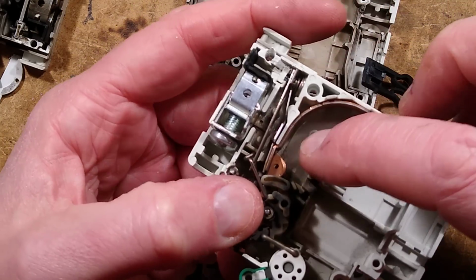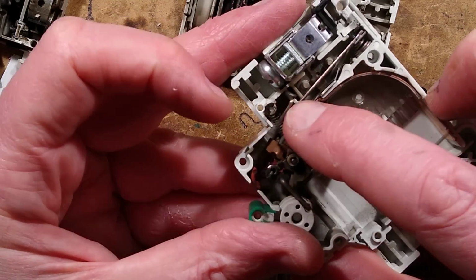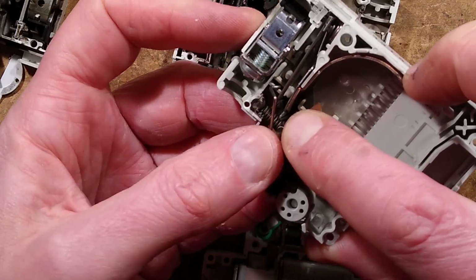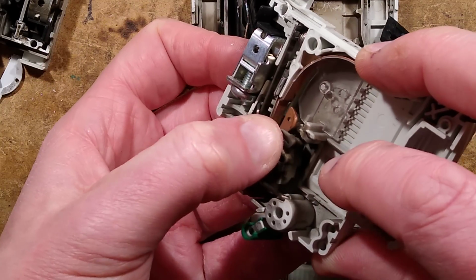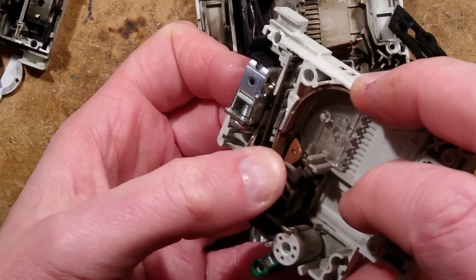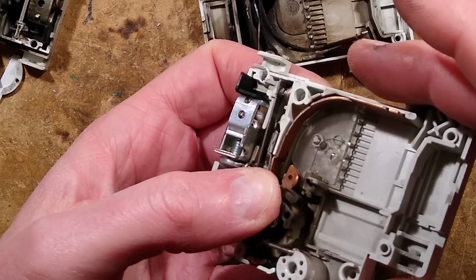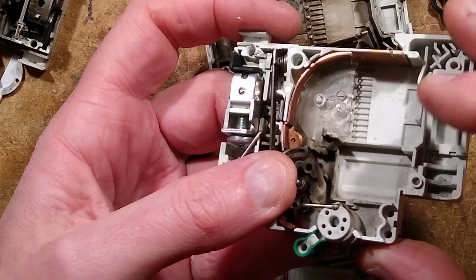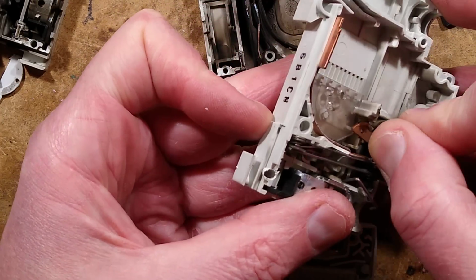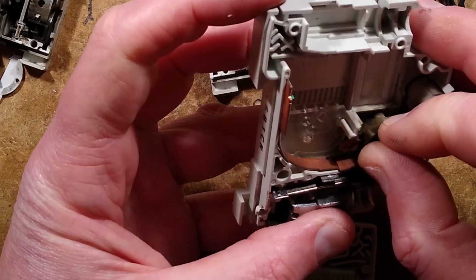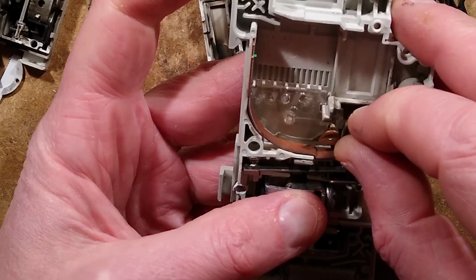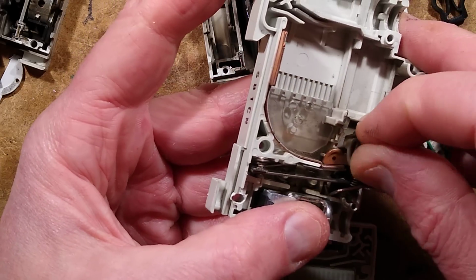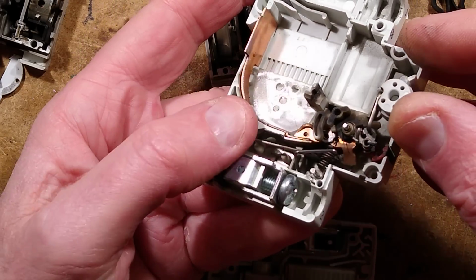Can you see that in there? I'll try and push it up. So I'm guessing, is that the contact? It looks like it, it's an unusual arrangement. And there's the guide that carries it up into the arc chute. I've not seen a contact like that before. It's quite strange. I'd normally expect to see sort of contact materials, but all I'm seeing is copper to copper, which is reasonable enough for a contact material.